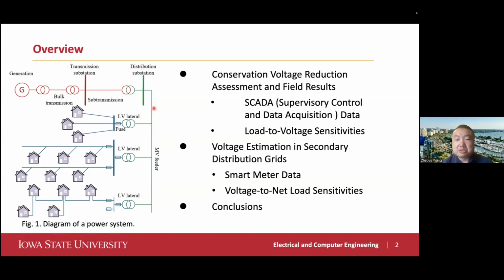So we will try to estimate the voltage in the secondary distribution grid using smart meter data. This uses voltage-to-load sensitivity—meaning, by injecting a certain amount of power P and Q, what's the impact on the voltage?